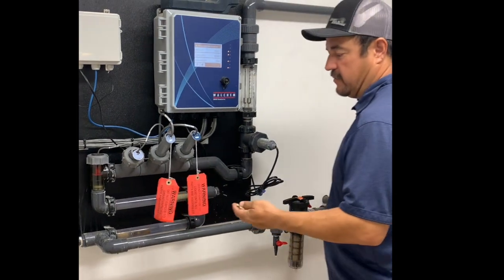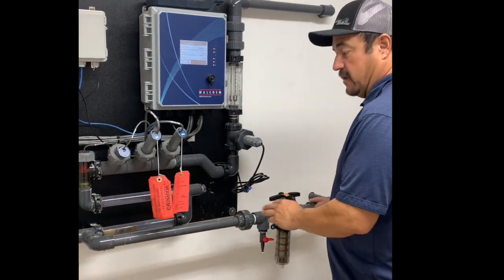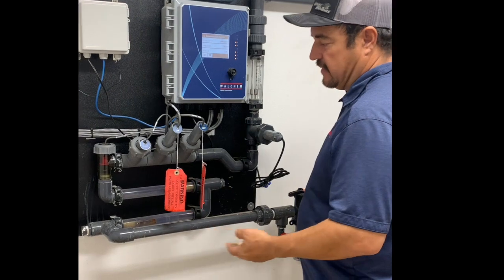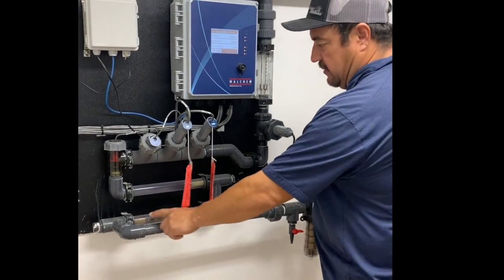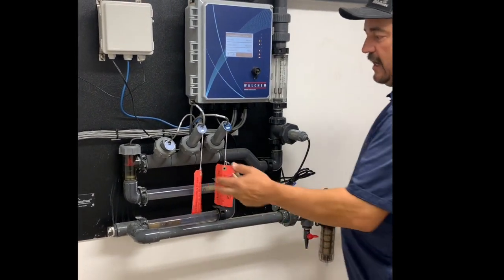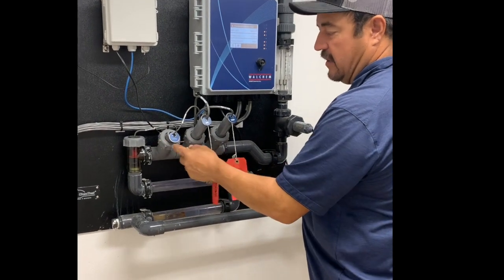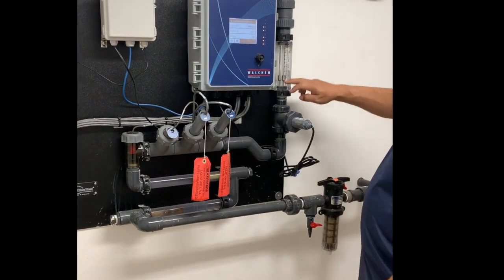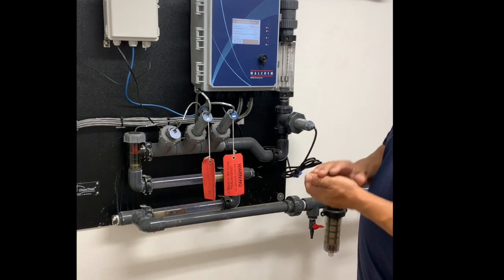We're getting ready to do our process calibration. You want to let it run for probably a minute or so just to get all the bubbles out of the line. Sometimes what will happen is if you do leave the air in there, it will throw off the reading of the probe. Want to make sure that we have good flow across the probe itself.